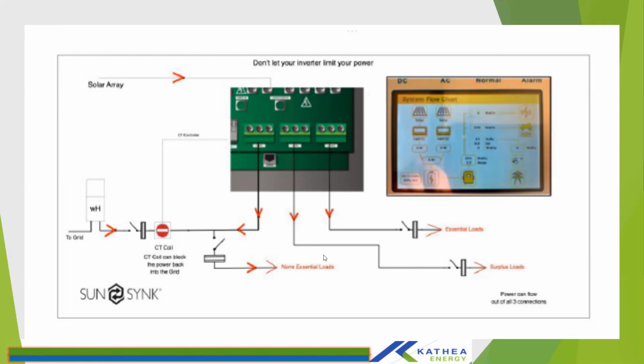And then the second port is the essential loads, which is the load output. On this port, as I've said, you need to keep your peak loads within the rating of the inverter. The inverter can, however, hold surge current for 10 seconds up to 2 times the rating, but you need to keep it within the rating so as to avoid the inverter overloading. And then the third port is the Aux port, which you can use as a generator input port. We'll look into that in detail in the following slides. Or you can use it as an output port if you have surplus PV after supplying your essential loads, usually in an off-grid scenario, and then you can use this port to supply your high power loads. That is if you have excess PV.